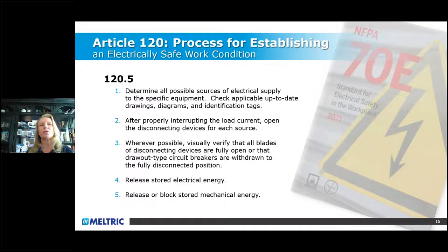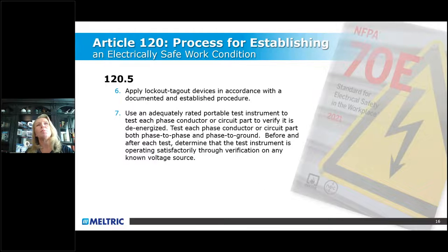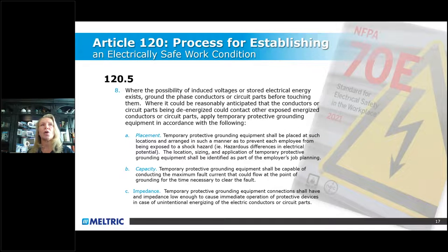After that, we start talking about releasing stored electrical energy, releasing blocked mechanical energy that could be present. Then we're applying the lockout tagout devices with the procedures that have been established, and using a portable test instrument to test each phase conductor. And finally, there is a long drawn out process of releasing induced voltages or stored electrical energy.